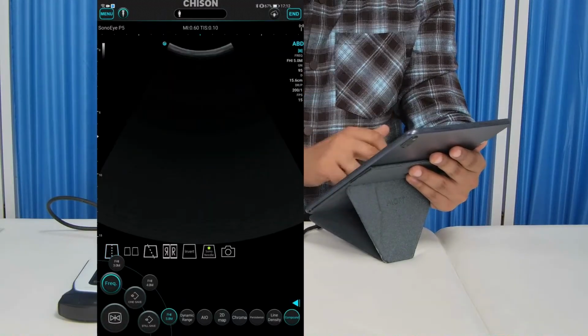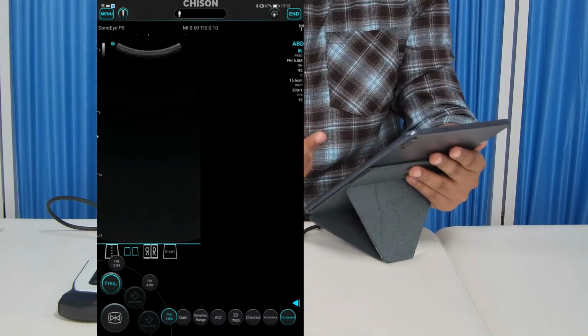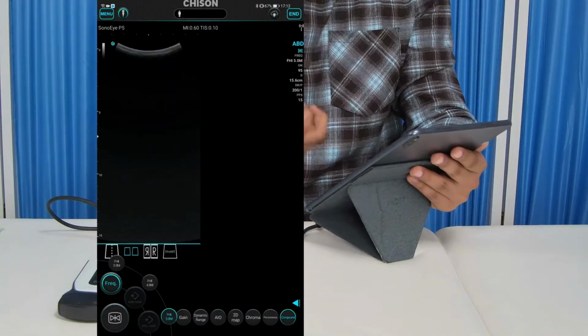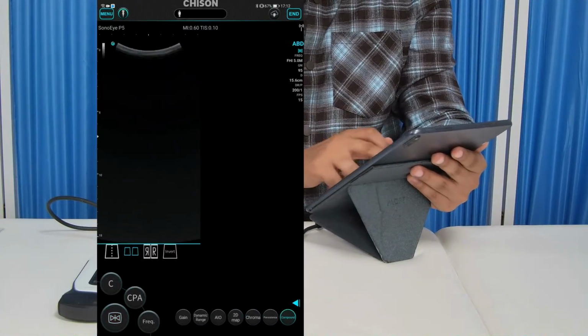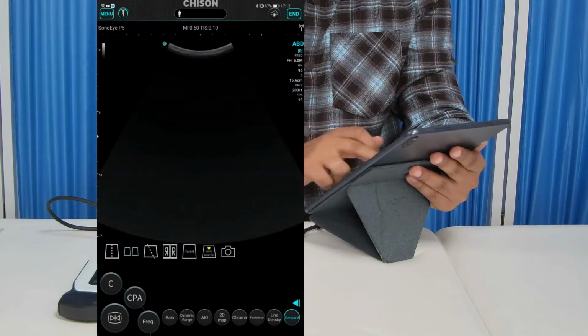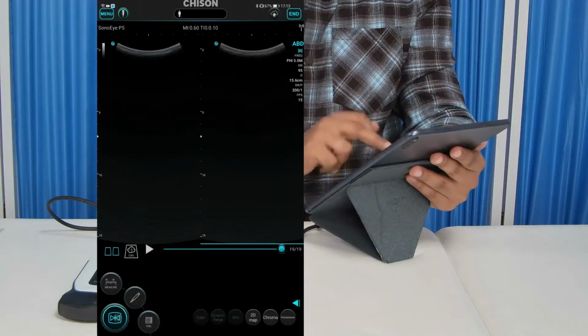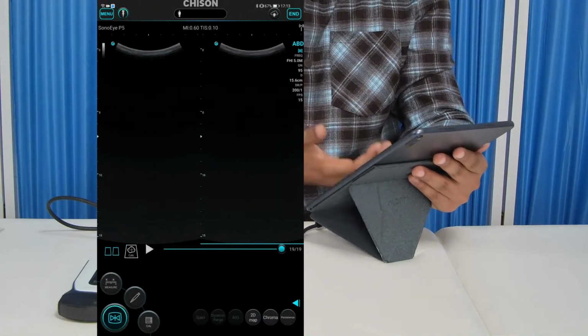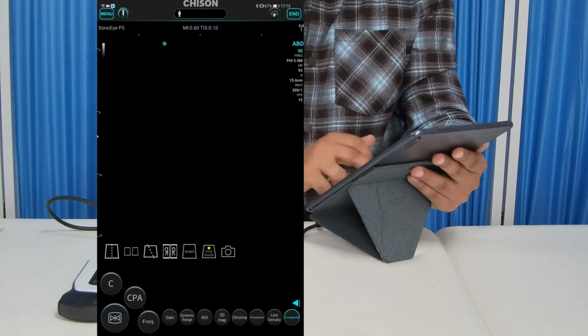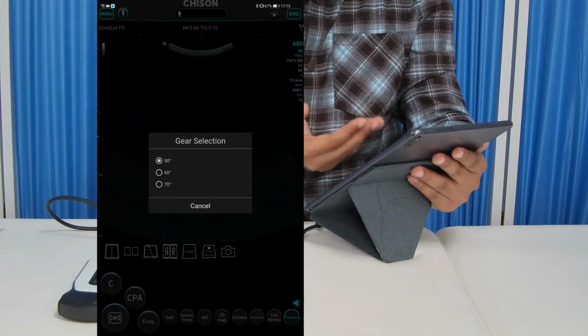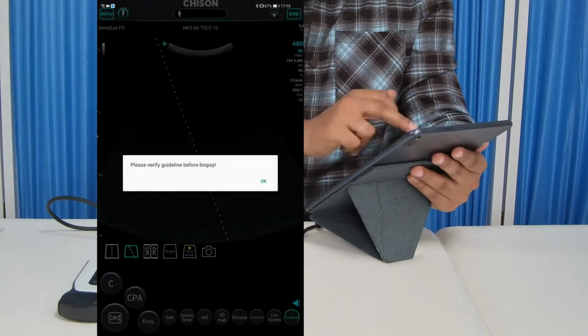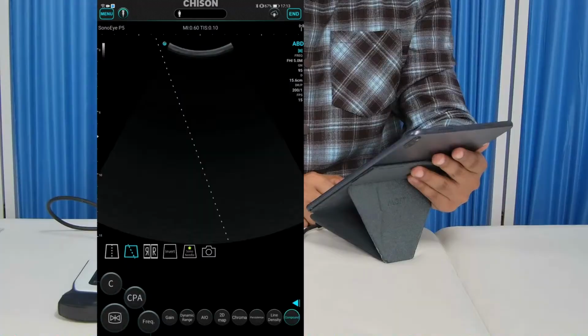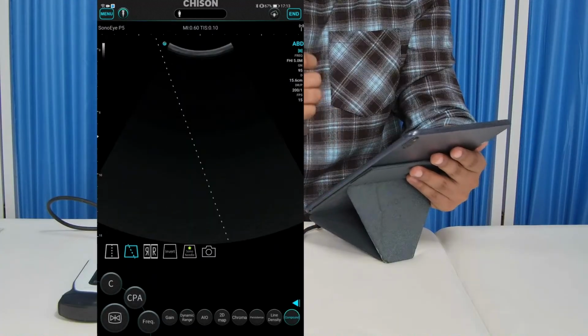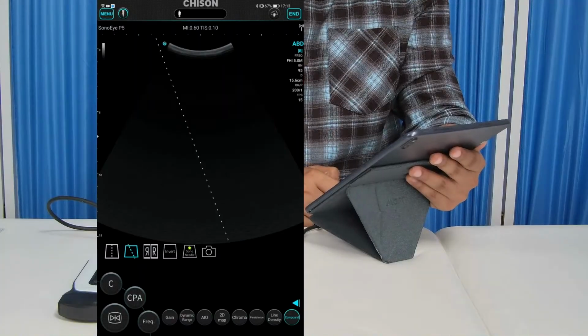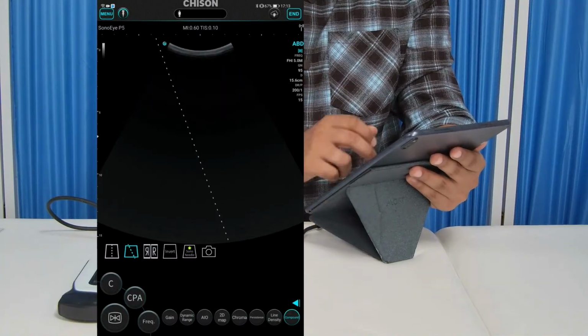Next, we have the dual mode. You can have two windows if you're scanning any structure which needs a volume measurement. So if you can see, I can change the image into dual imaging, and then I can scan two different views, sagittal and transverse view. Next, we have the biopsy needle angle marker available, whether you're using 50 degrees, 60 degrees, or 70 degrees, you can choose over there. And then you can use the biopsy bracket with the transducers to improve needle visualization and needle enhancement while doing any kind of interventional procedures.